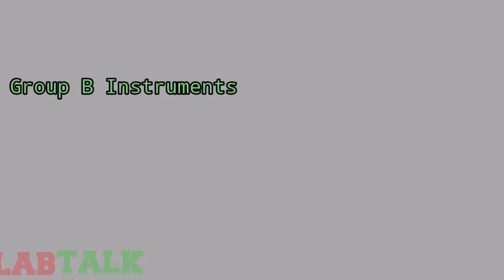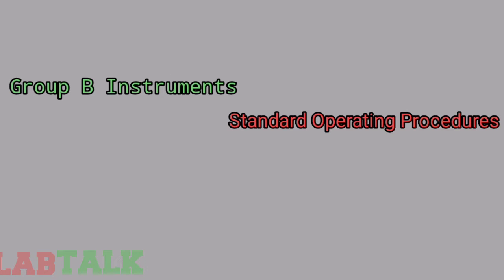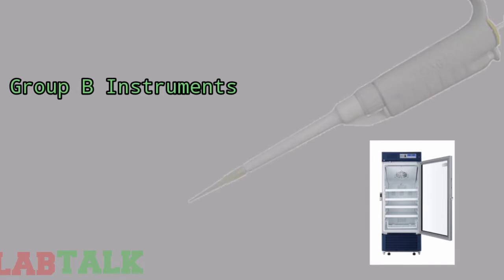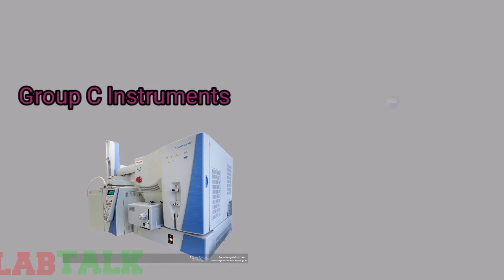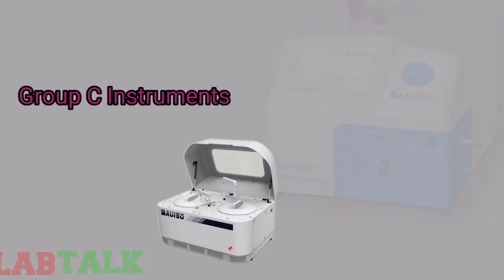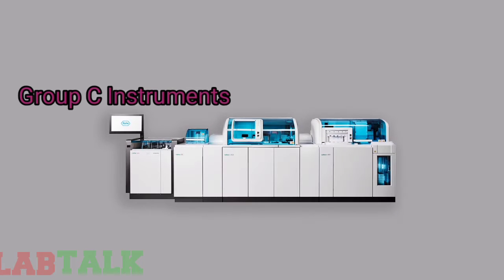Group B instruments. The conformance of Group B instruments to user requirements is performed according to the instrument standard operating procedure. Their conformity assessments are generally unambiguous. Examples in this category include balances, incubators, infrared spectrophotometers, melting point apparatus, pH meters, pipettes, refrigerators, thermometers, titrators and viscometers. Then there is a third category, Group C instruments. Conformance of Group C instruments to user requirements is highly method specific and the conformity bounds are determined by their applications. Examples in this category are the state-of-the-art atomic absorption spectrophotometer, differential scanning calorimeters, densitometers, electron microscopes, elemental analyzers, gas chromatographs, high pressure liquid chromatographs and modern-day automated analyzers used in the clinical laboratory.